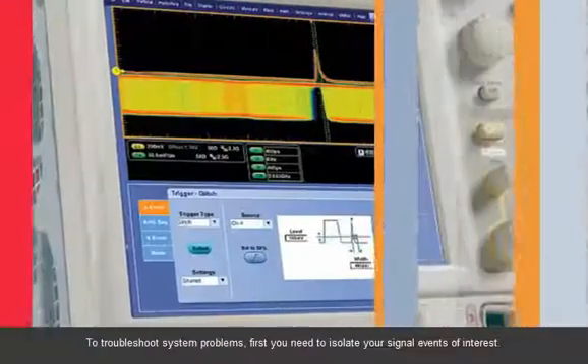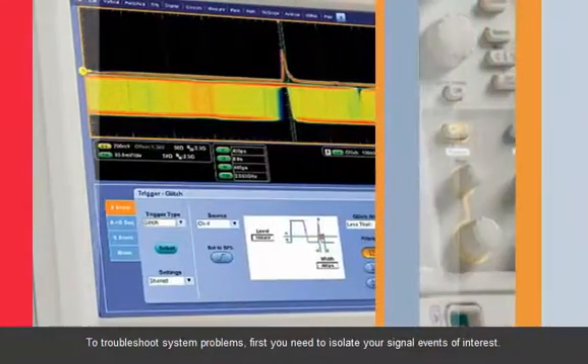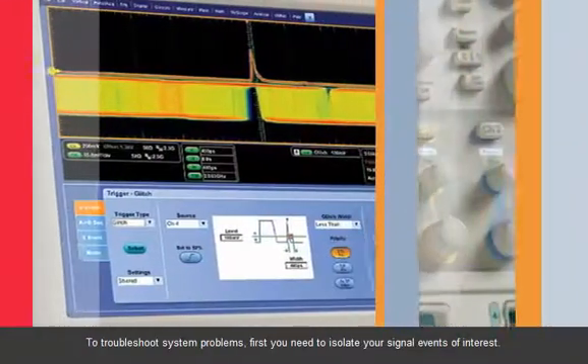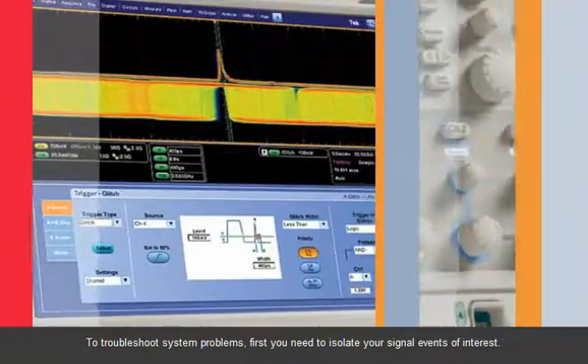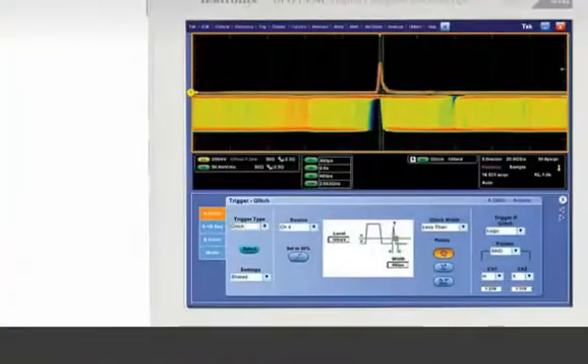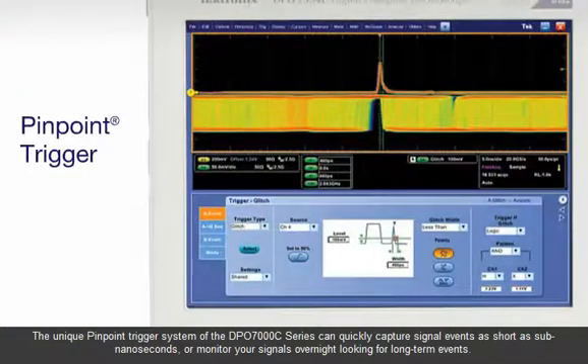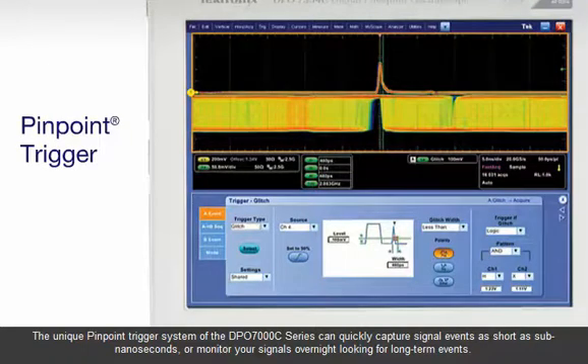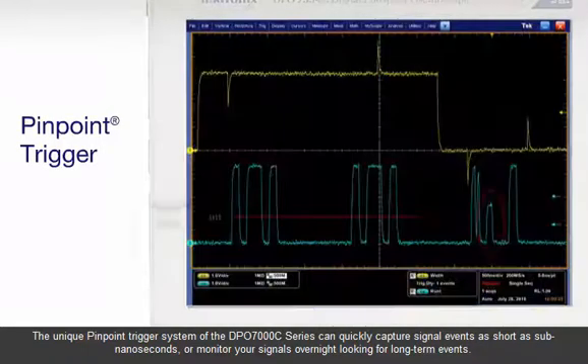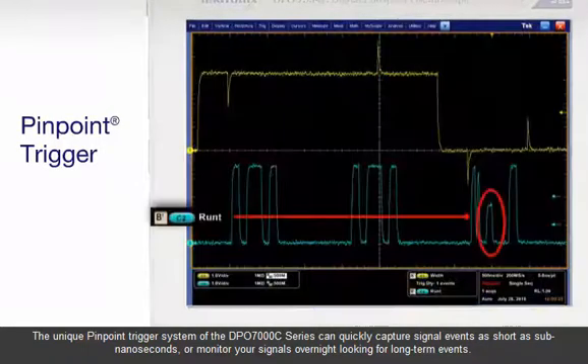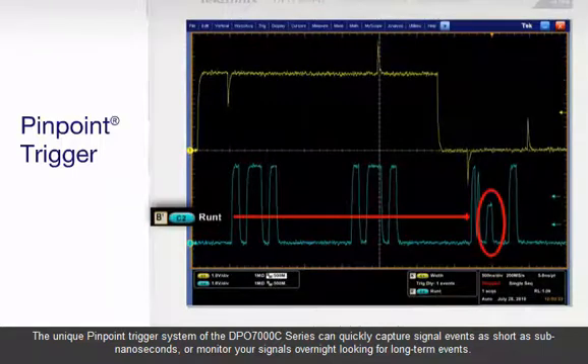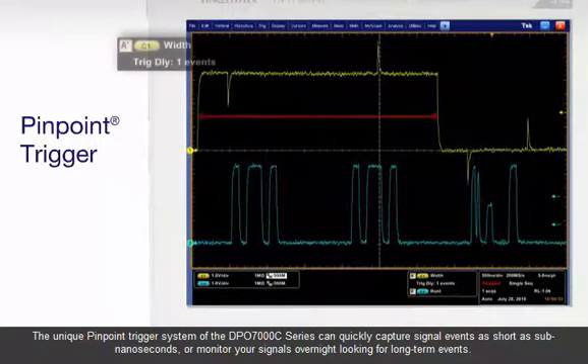To troubleshoot system problems, first you need to isolate your signal events of interest. The unique pinpoint trigger system of the DPO7000C series can quickly capture signal events as short as sub-nanoseconds or monitor your signals overnight looking for long-term events.